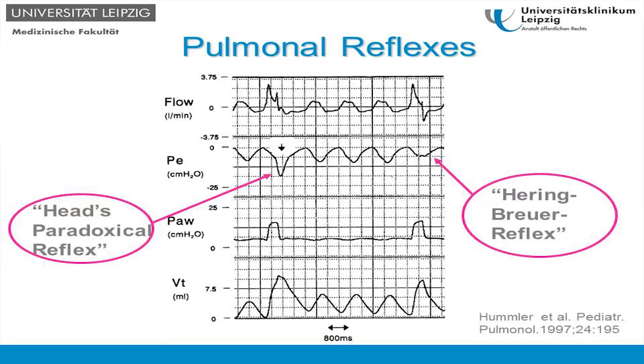The Hering-Breuer reflex means that a big breath disables the patient's own efforts, and the esophageal pressure drop is much smaller because the patient feels, I have had enough tidal volume, I stop inhaling here, and this is called the Hering-Breuer reflex. The opposite is the Head's paradoxical reflex, which means that there's an especially big breath generated by machine breath, and both reflexes can be observed in the unit especially when you are using synchronized modes of ventilation.